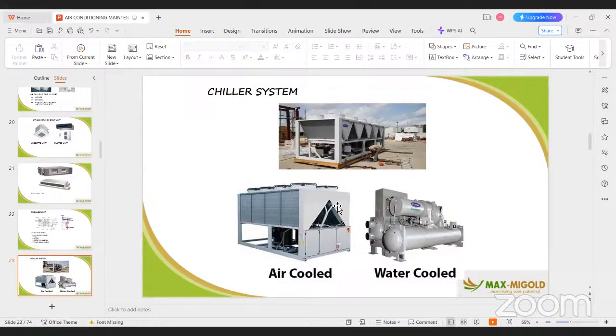Then we have two types of the chiller system: the air-cooled chiller and the water-cooled chiller. The cheapest of these two is the air-cooled chiller. The air-cooled chiller uses the air within the environment to cool the compressor that is working and every other component within it. While the water-cooled system requires a cooling tower, requires another pump. It's a big form of installation. If the cooling tower breaks down, the water-cooled system will not function.